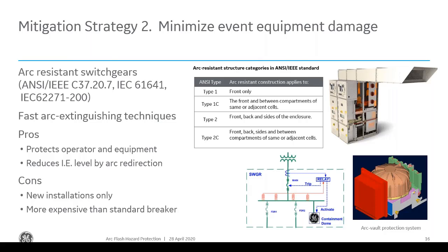What it does is redirect arc energy out of the equipment through ducts or vents, away from the operators. You can see in this picture the duct or vent on the top, which goes to a location where personnel would not be in the vicinity. All primary compartments are provided with pressure relief flaps located on the top side of the switchgear, so any overpressure inside a compartment caused by an internal arc is released through these flaps. There are IEC and ANSI standards defining the required type tests to be able to say you're ANSI Type 1 or, for example, ANSI Type 2C. With Type 1 switchgear, an operator can approach the front of the switchgear lineup and won't have any exposure to any type of arc flash or arc blast.